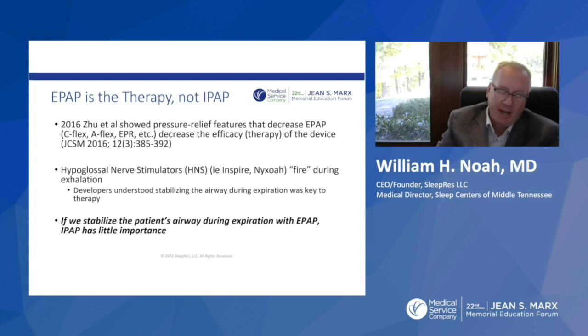Number two, it's got to be able to clear the CO2 or the exhaust from the circuit so the patient doesn't rebreathe, like our question about Dr. Smith. So it's the expiratory pressure that clears the gas. As you are breathing out during exhalation, it's the pressure in the circuit during exhalation that is determining the flow or the intentional leak out the little hose. And so lowering EPAP not only lowers therapy, it increases the risk of rebreathing. IPAP provides little protection from rebreathing.